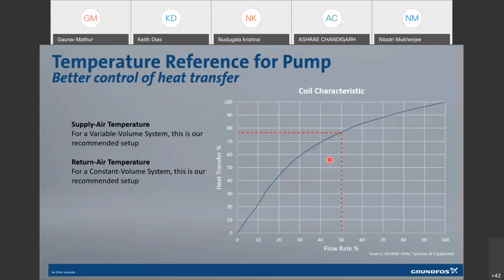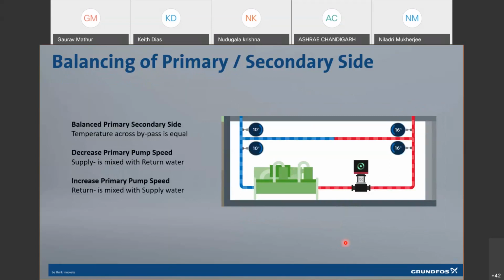But if you look at the coil characteristics, and I'm sure you all are aware that you are able to achieve 80% heat transfer at 50% flow. Now, if you connect it with the system curve, you can see the amount of savings which are possible, because here you are able to achieve a heat transfer at a much lower flow rate, and that ensures that the amount of savings are manifold when you have part load conditions happening, which is typical. If you look at any load profile, you will be running at 100% not more than 5% of the time. Most of the time the load is lower than 100%, and that is where you are able to see a huge amount of savings happening.